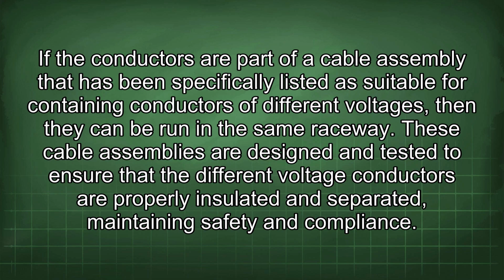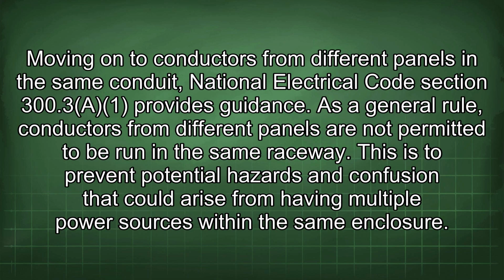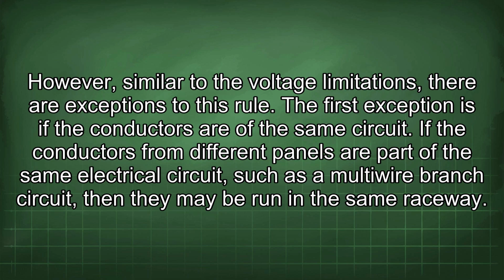Moving on to conductors from different panels in the same conduit, National Electrical Code Section 300.3(A)(1) provides guidance. As a general rule, conductors from different panels are not permitted to be run in the same raceway. This is to prevent potential hazards and confusion that could arise from having multiple power sources within the same enclosure. However, similar to the voltage limitations, there are exceptions to this rule.